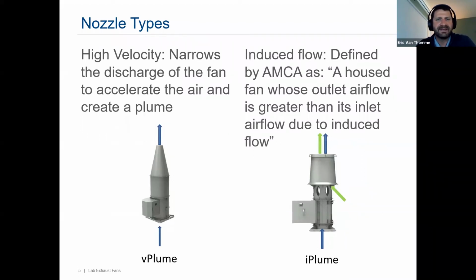The typical nozzle types that are pretty popular in the industry, there's really two. One being the high velocity, this is quite simply a narrowing of the discharge of the fan. And what that does is accelerates the air and creates a virtual stack or a plume. There's also an induced flow style. And this is actually one that AMCA, our trade association, has gone ahead and created a certified ratings program for, because in a typical fan performance, you're going to measure this inlet flow and you can measure this outlet pretty easily. But this induced flow here, shown by this green arrow, is a little bit more difficult to measure.